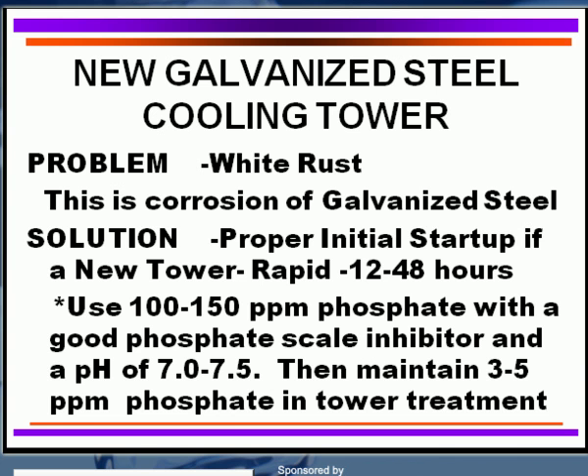Another technique is for a rapid establishment of protection on the galvanized steel, which can usually occur within 12 to 48 hours. This is done by utilizing a high level of phosphate in the cooling tower water — in the range of 100 to 150 parts per million of phosphate — with a good phosphate scale inhibitor so you don't get deposits. Maintain your pH at about seven to seven and a half. Once that has been established, maintain at least three to five ppm of phosphate in the standard continuing cooling tower water treatment program.